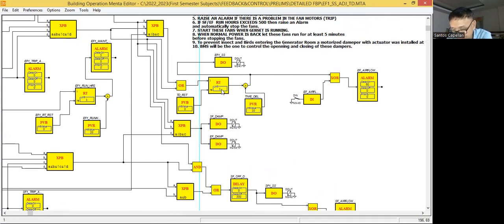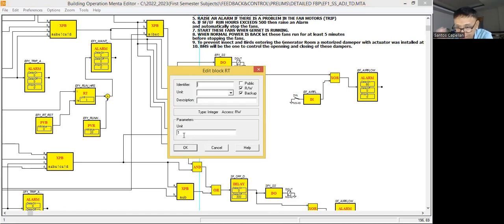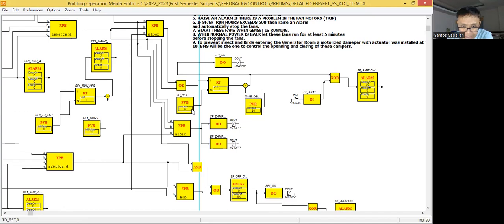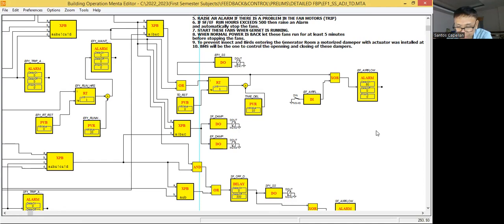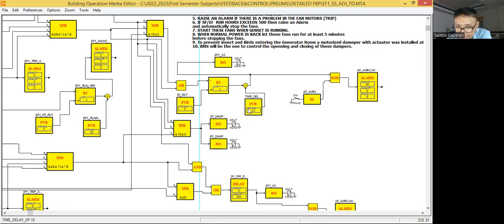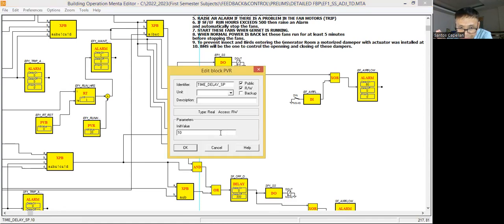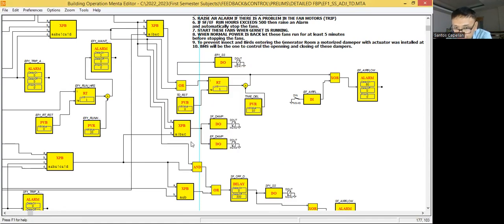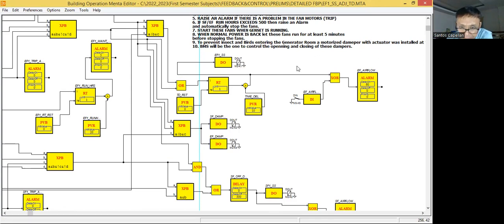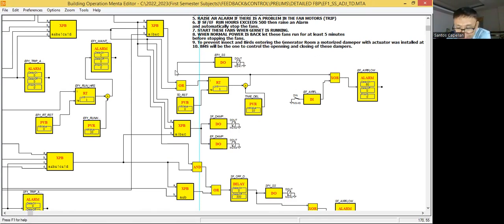I used a runtime block. In my runtime block, in the units, I've used one here, so this is for minutes. Then I have a PVR reset to reset the accumulated time. Then I'm using one operator. I have here a PVR parameter value real wherein the user can adjust the value here or the initial value in the graphics.